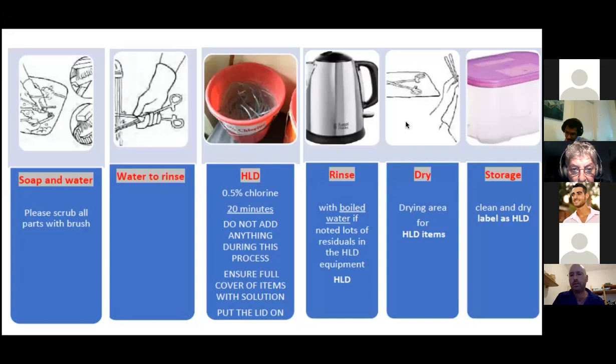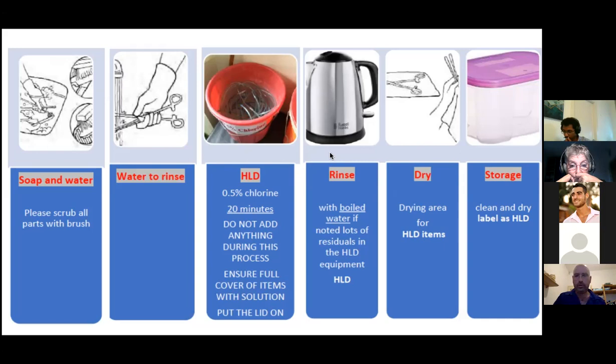And I want to emphasize this because from what I heard, it can be a problem in some of the units: you need to really take good care of the drying part and check the tubes before storing them in a clean and dry container, so that the next baby receives clean and dry tubes. So give it as much time as it needs to dry. And of course, we need to do it after every use. When we have finished the use of the CPAP for one patient, we clean the parts and wait for the next patient.